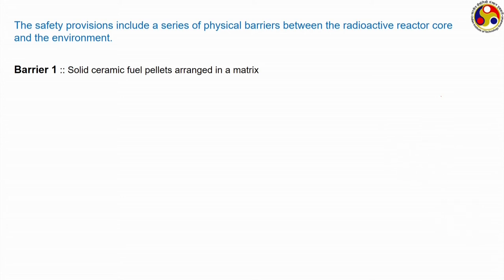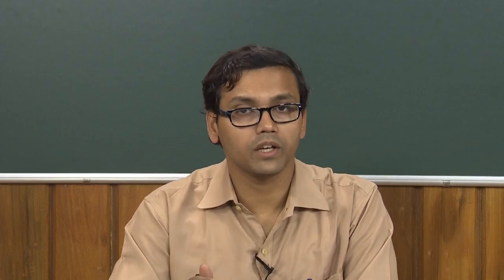The second barrier is the cladding — the jacket around the fuel. One key function of cladding is to prevent the release of radioactive fission products to the coolant stream. Cladding can be made of Zircaloy, Magnox, or in certain situations stainless steel. Being strong and generally non-permeable metallic sheets, they efficiently prevent leakage of fission fragments.